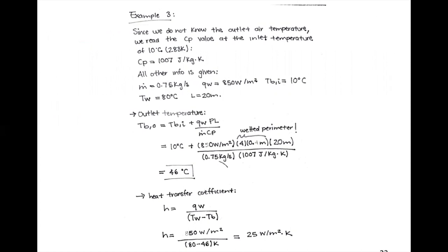For the outlet temperature, using the equation for a surface exposed to constant flux: T-bulk-out equals T-bulk-in plus the flux multiplied by the wet perimeter multiplied by the length, divided by mass flow rate times CP. We get T-bulk-out of 46°C. Since we have a square duct, the wet perimeter is straightforward: 4 × 0.4, which is what's used in the calculation.